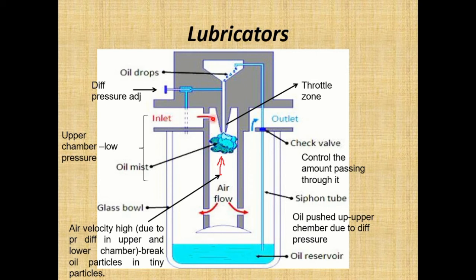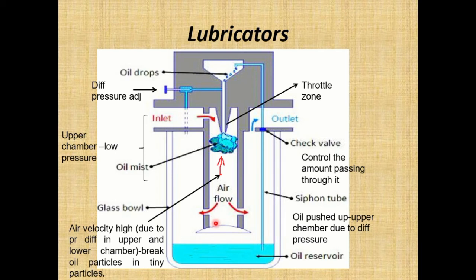Because air velocity is high, it breaks down the oil mist and carries oil particles with it toward the outlet. Some oil particles are collected at the bottom section, and a baffle ensures oil never enters the main section. This is how the lubricator works — the complete operation is based on the pressure difference in the chamber.